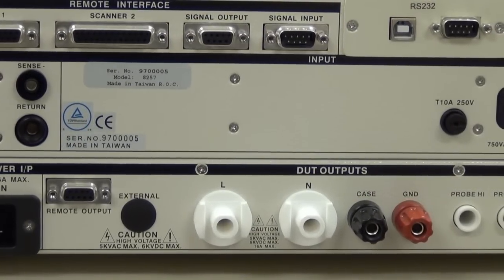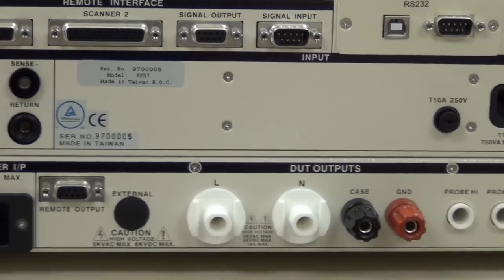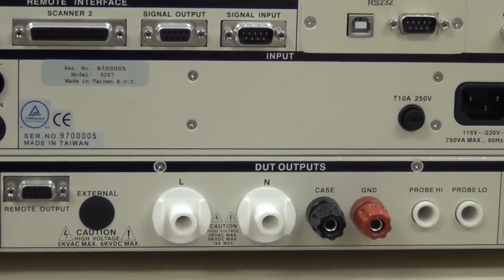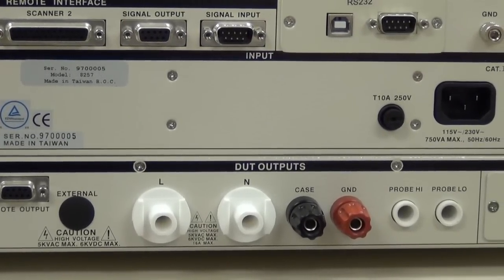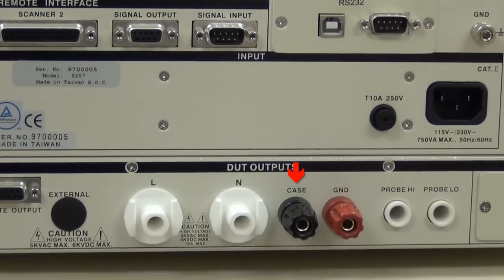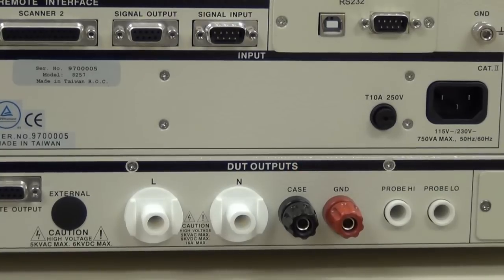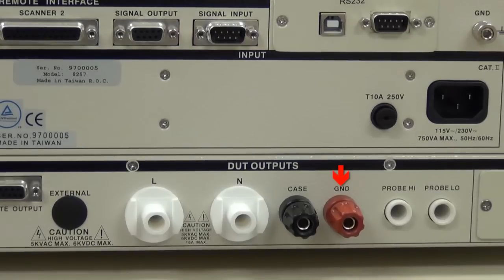The case connector is used to attach the return lead to the DUT case or chassis. This provides a return path for the ground bond, DC continuity, dielectric withstand, and insulation resistance tests. During a line leakage or functional run test, this terminal is isolated from the test circuits. The ground connector is used to attach the adapter box ground or earth lead to the instrument.